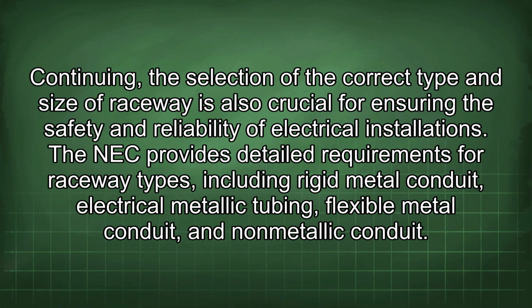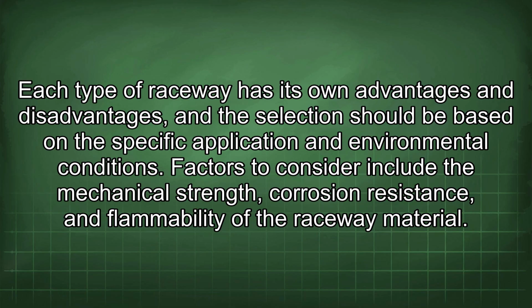Continuing, the selection of the correct type and size of raceway is also crucial for ensuring the safety and reliability of electrical installations. The NEC provides detailed requirements for raceway types, including rigid metal conduit, electrical metallic tubing, flexible metal conduit, and non-metallic conduit. Each type of raceway has its own advantages and disadvantages, and the selection should be based on the specific application and environmental conditions. Factors to consider include the mechanical strength, corrosion resistance, and flammability of the raceway material.